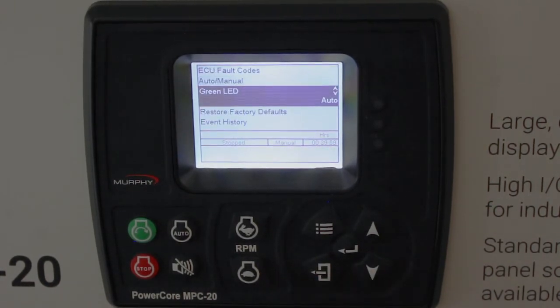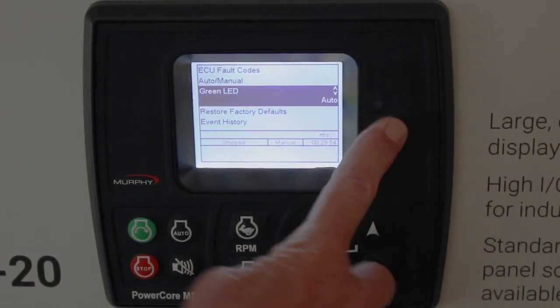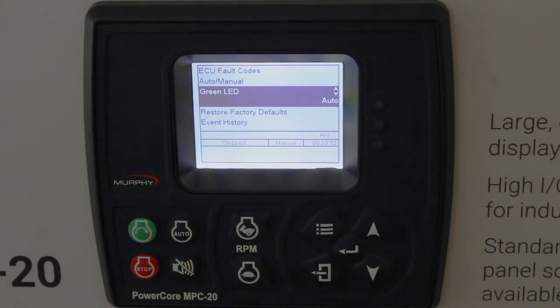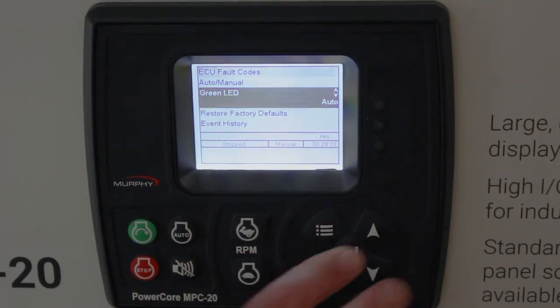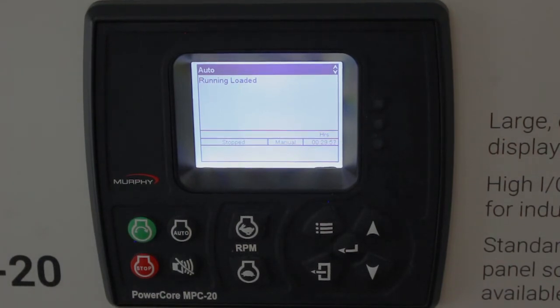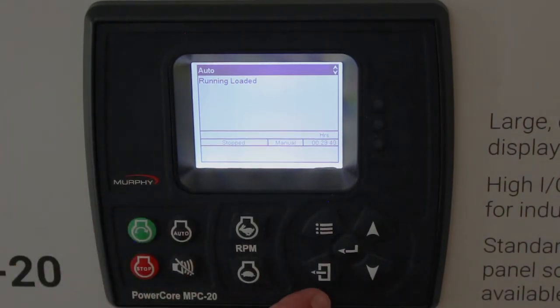Green LED — there are three LEDs on the side of this controller: red, amber, and green. The red and amber are standard with electronic diesels — when they throw an amber or red code, or there's an external fault that's a shutdown or warning, the red or amber LED lights up. The green LED from the factory defaults to lighting up when you're in auto. You can also choose 'running loaded' — so if you want to know the engine is through warmup and fill mode and actually doing work, you can light the green LED at that point. It defaults to on whenever you're in auto.